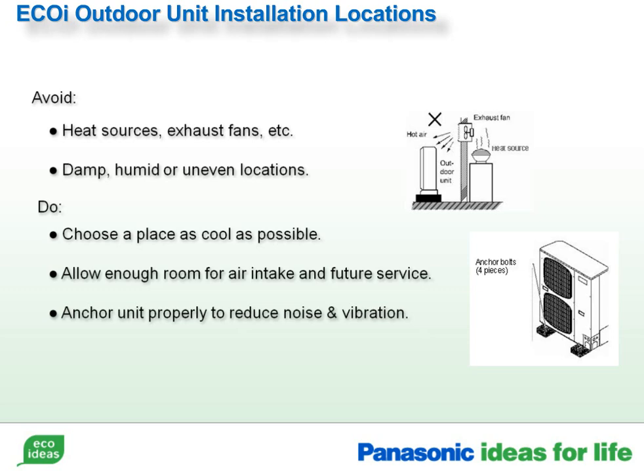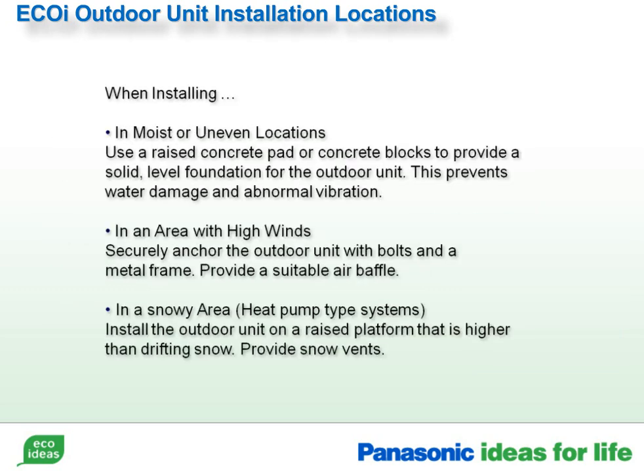Always anchor the unit properly to reduce noise and vibration. When you are installing a condenser in a moist or uneven location, use a raised concrete pad or blocks to provide a solid, level foundation. This will prevent water damage and abnormal vibrations. In areas that are subject to high winds, securely anchor the outdoor unit with bolts to a metal frame, and provide an air baffle. Snow drifts can also affect the performance of the condenser.